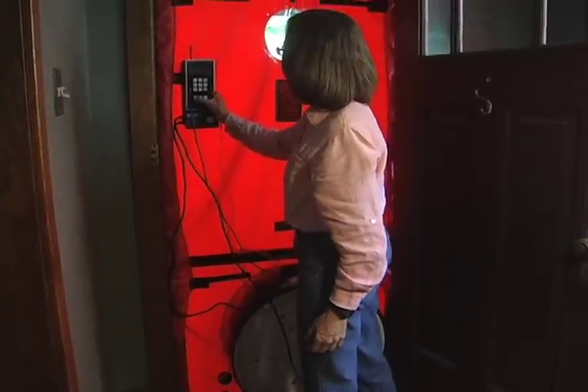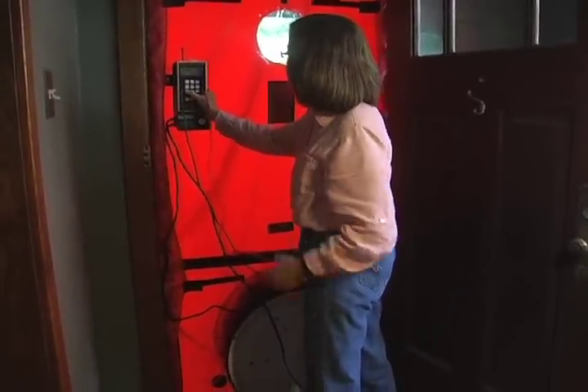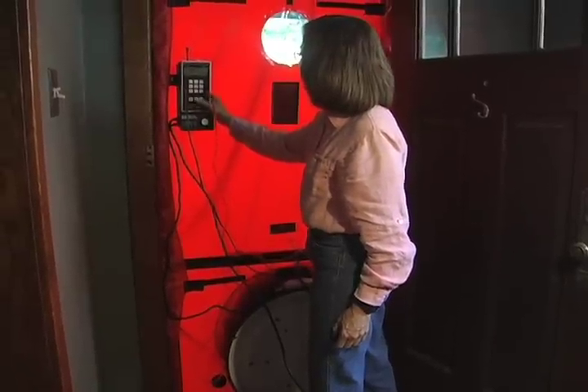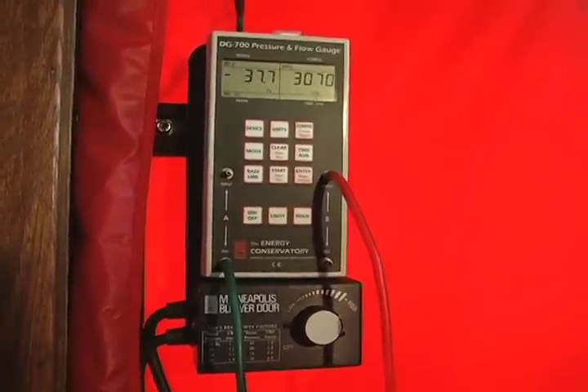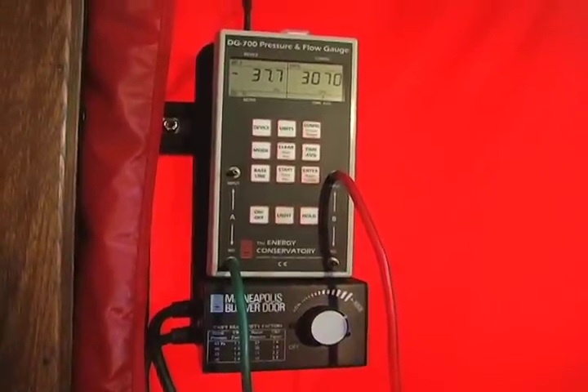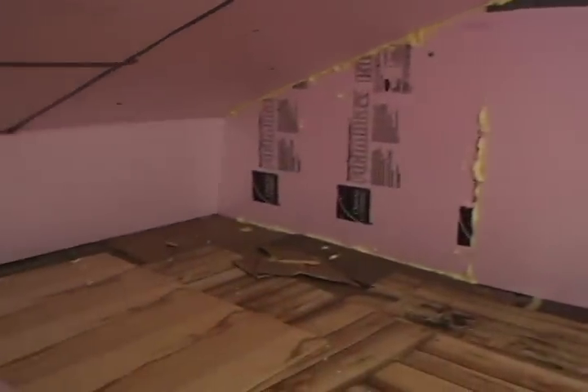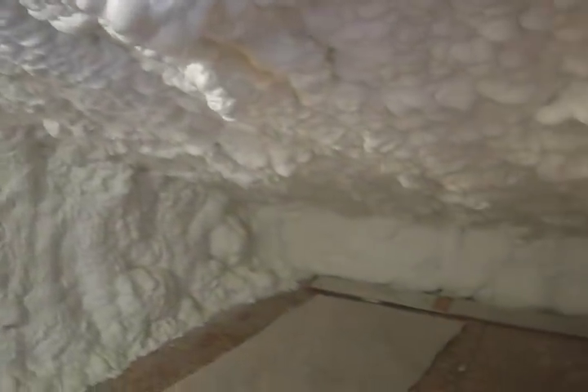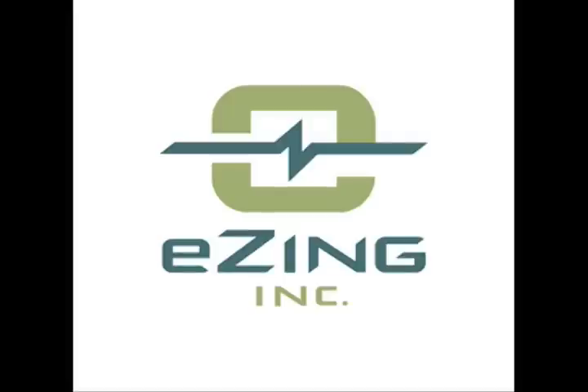Our final blower door measurement was 3,384 CFM at 50 pascals, as compared with the pre-air seal measurement of 6,446 CFM at 50 pascals. That represents a 48% reduction in air leakage. After the drywall penetrations from the insulation work are sealed and painted, we expect a measured reduction above 50%. Air leakage can be further reduced when the clients decide to fill the first floor walls with cellulose. This was a very successful outcome and should translate to a comfortable second floor for the homeowners.